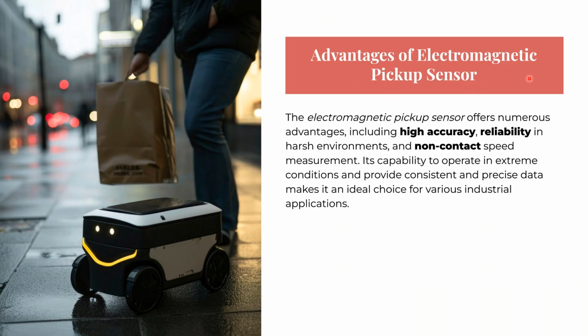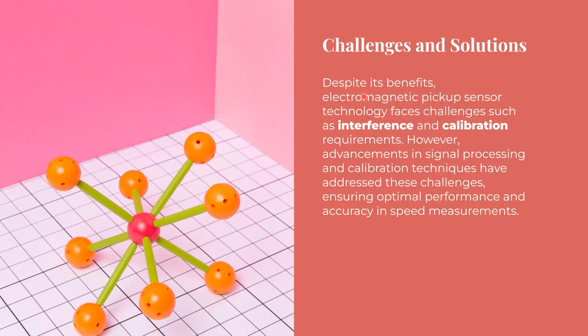Advantages of electromagnetic pickup sensors: very high accuracy, reliability, and non-contact speed measurement. The challenges it faces are interference from electromagnetic field lines and the calibration required to get the signal from those feeble induced signals. These are some challenges. However, the advanced signal processing unit in the system has addressed these challenges, which ensures optimal performance and accuracy in speed.